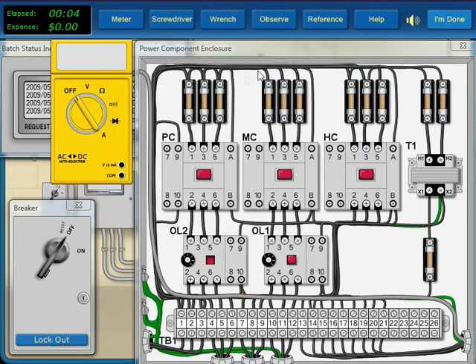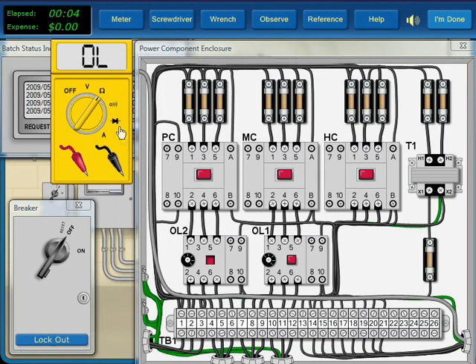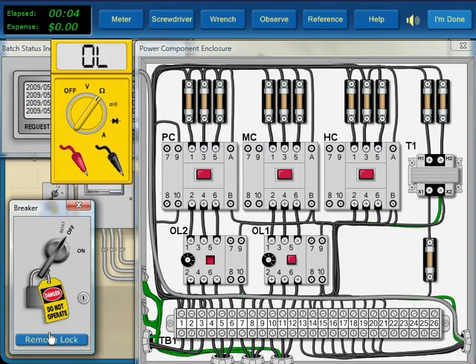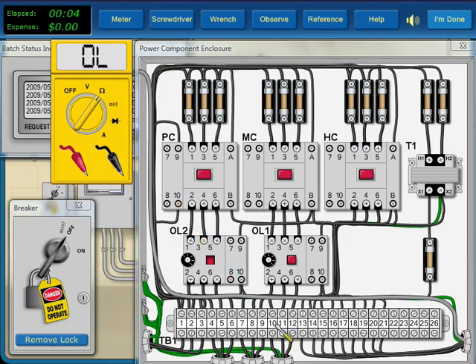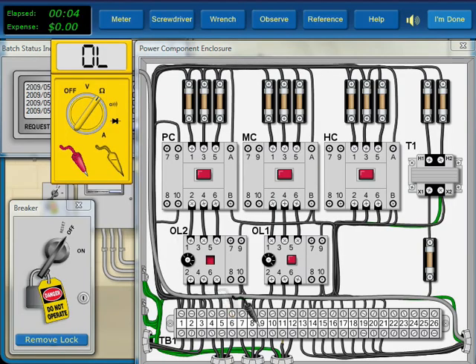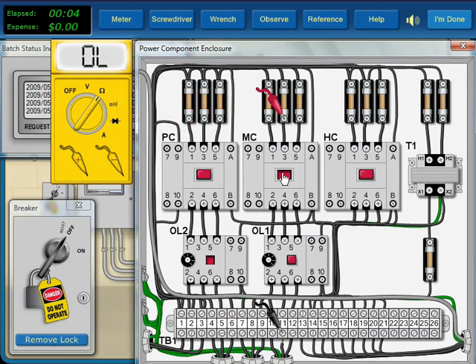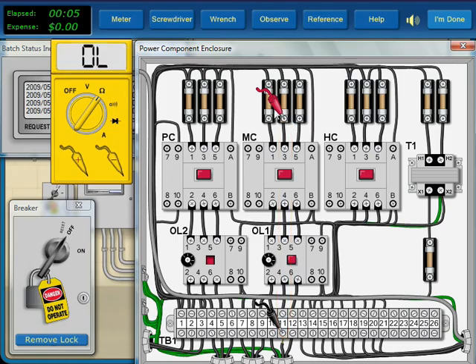To find an open in a three-phase motor circuit, an ohmmeter is the best choice. So we need to lock out the circuit. Next, we sectionalize the circuit where it leaves the power box by disconnecting a wire and measuring from there to the fuse with the contactor closed. We read infinite resistance. This means that the open is within the control box.